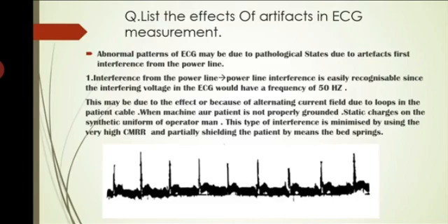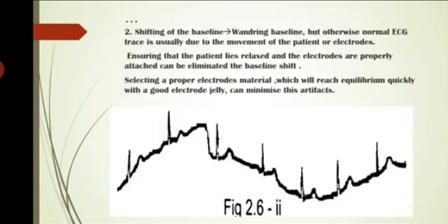Static charges on the synthetic uniform of the operator can also cause it. This type of interference is minimized by using a very high CMRR and partially shielding the patient by means of the bed springs. So by using this, we can avoid this interference.